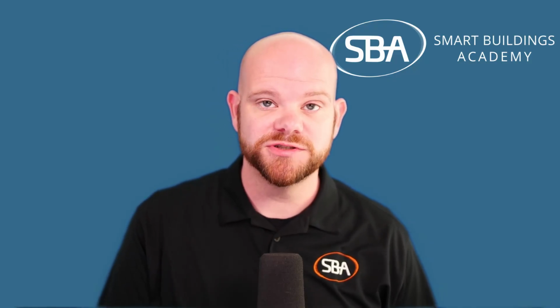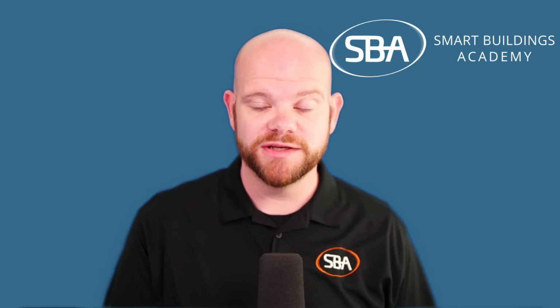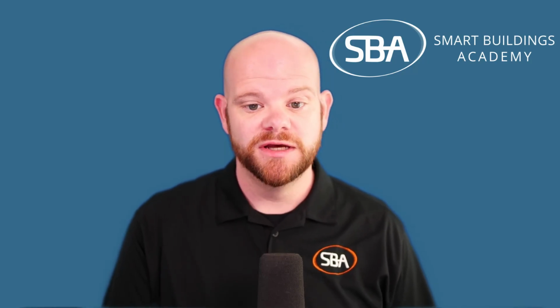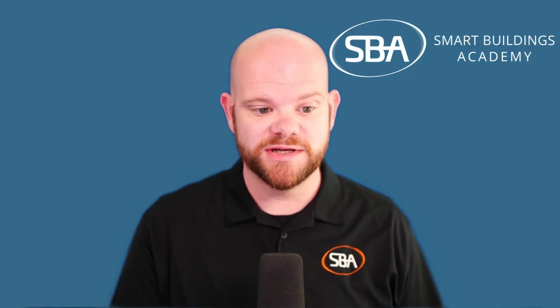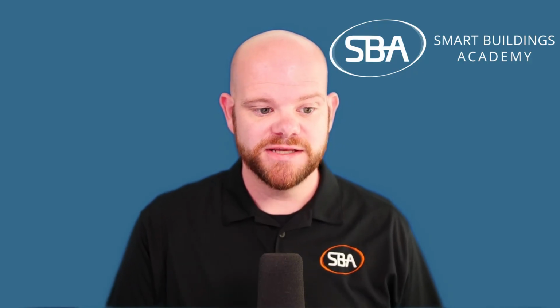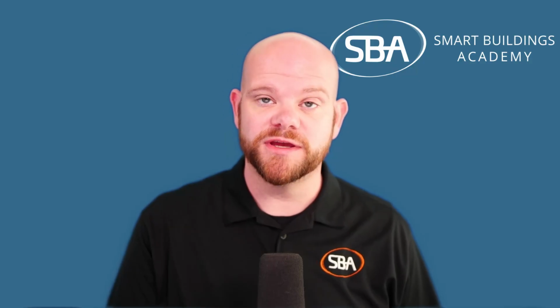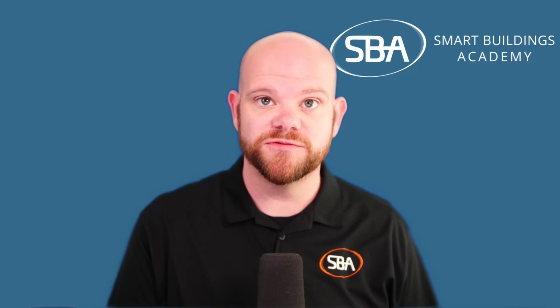So now let's talk about the BAS startup roadmap. For number one here, we're going to talk about the pre-startup review. When we do our pre-startup review, we need to check all the documentation and make sure we have all of our materials ready. So tools, documentation, drawings, all these things. Make sure we have all this stuff ready and available so that when we go to start, we have it. We're not wasting time trying to find it. Next thing, number two here, is field verification. This is going to be physical device verification of every device on your system.